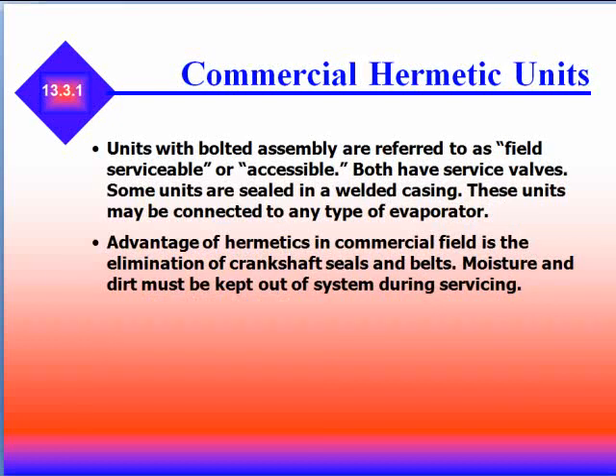Commercial hermetic units are usually bolted together and referred to as field serviceable or accessible. Both have service valves. Some units are sealed in a welded casing, and these units may be connected to any type of evaporator. The advantage of hermetics in the commercial field is the elimination of crankshaft seals and belts. Moisture and dirt must be kept out of the system during servicing.